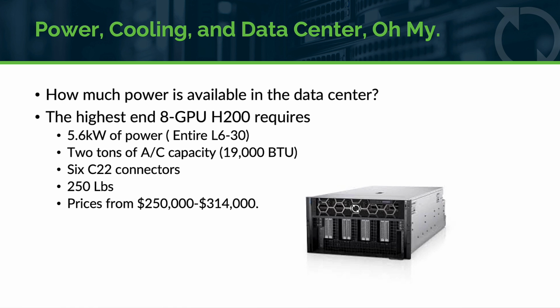This particular server needs about 6 kilowatts, which is a L630 circuit. That's not uncommon in a data center, pretty common actually. But you need to make sure that you have a rack to put it in. It's a couple 250 pounds. Needs 19,000 BTU of cooling.